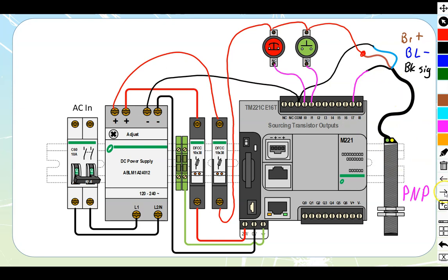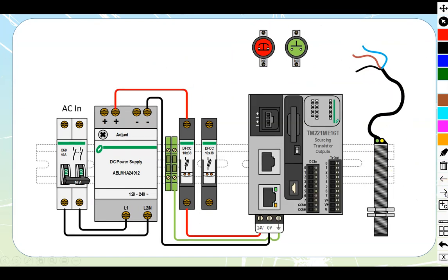Okay, that's one of our cartridge styles. Let's take a look at the monolithic style. Exact same concept as before, just a slightly different body. We start with the AC in, we take that AC, we convert it into DC through a DC power supply, and then we take that DC power supply, we fuse our live line, and we bring it into our power supply that we have over here. This one's got the shield in place sitting over top so you can see all the ratings: 24 volt, 0 volt, and the ground. We have it grounded down. All that's covered inside the first video if you need more details on it. The rest of this is going to be done the same as before.